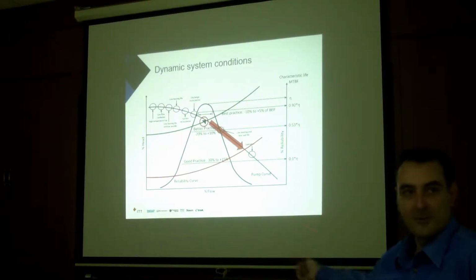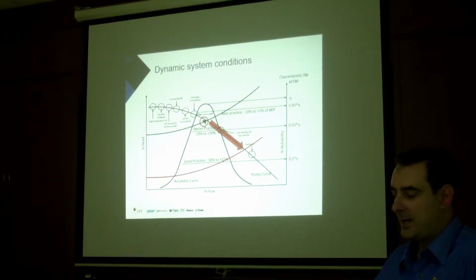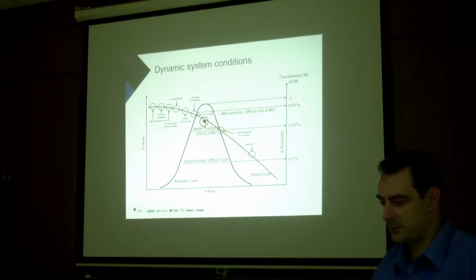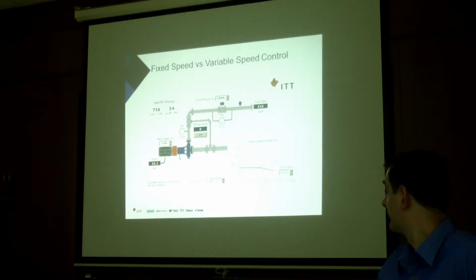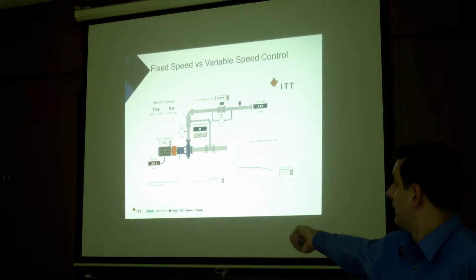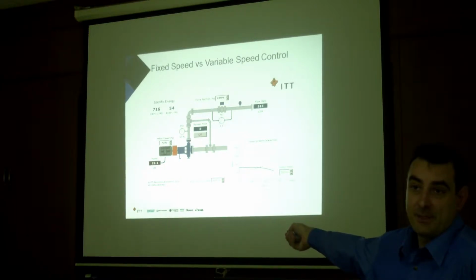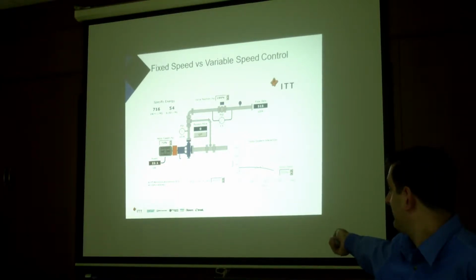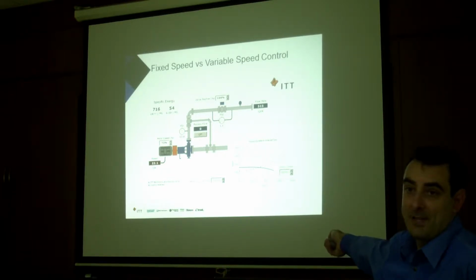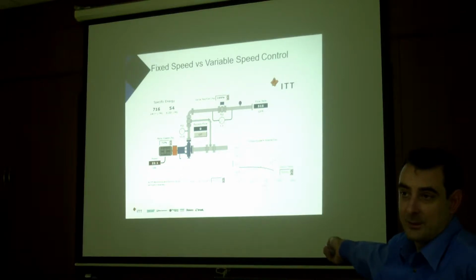We just keep pushing further and further down. If you remember from this slide, I've lowered the speed. See the pump curve? This is the original. The maximum flow is higher. Once you slow the pump down, the maximum flow is lower.